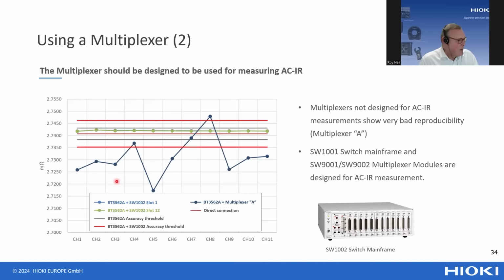If you look at the other line, this is a combination of our battery tester with a multiplexer that was not properly designed for ACIR measurement. You can immediately see a wide spread of measuring results, meaning the reproducibility is not okay. In this kind of situation, nothing can help you, because the measurement result is very unpredictable.